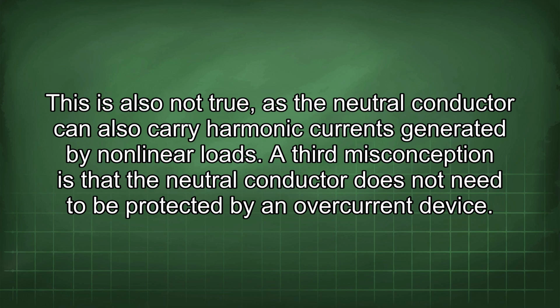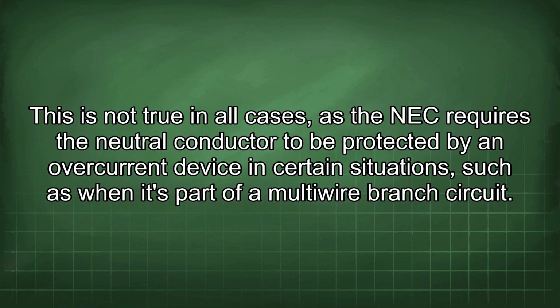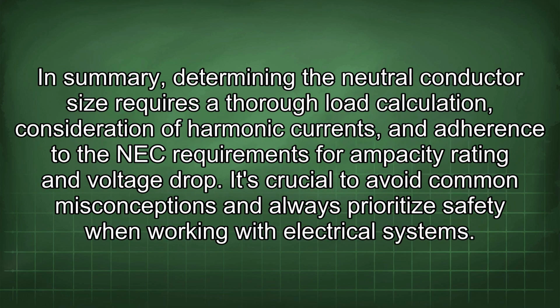A third misconception is that the neutral conductor does not need to be protected by an overcurrent device. This is not true in all cases, as the NEC requires the neutral conductor to be protected by an overcurrent device in certain situations, such as when it's part of a multi-wire branch circuit. In summary, determining the neutral conductor size requires a thorough load calculation, consideration of harmonic currents, and adherence to the NEC requirements for ampacity rating and voltage drop.